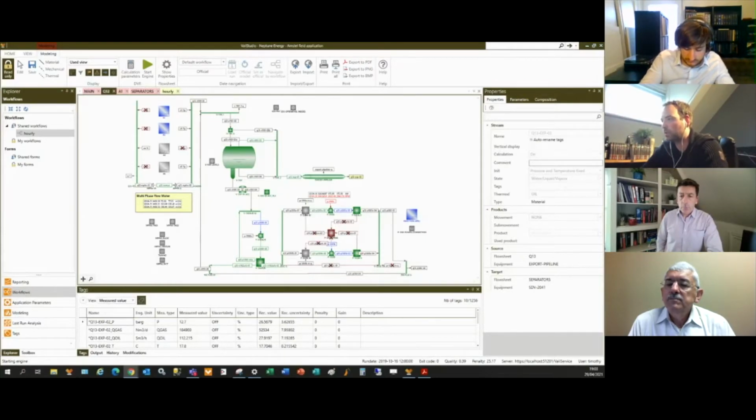And this is also one of the biggest challenges that we had for this Cherry Valley Hash project, that we had to estimate what the uncertainty was of all these 120 measurements, taking into account DP ranges, if they were calibrated, if the conditions are harsh for this meter. So there's a lot of uncertainty in the determination of the uncertainty already. So yeah, that's something that we need to deal with.